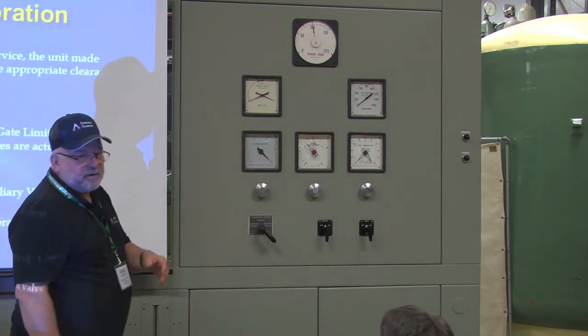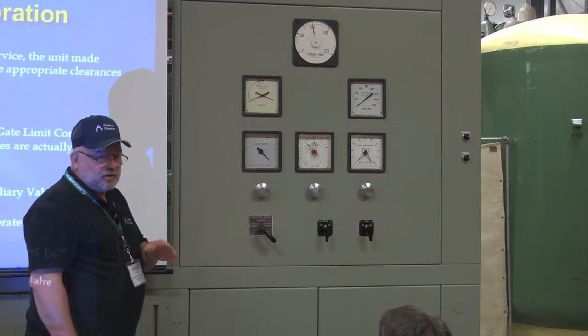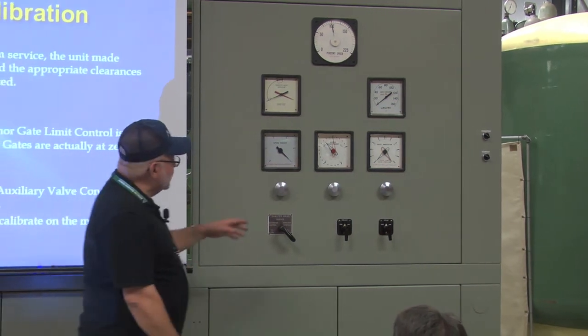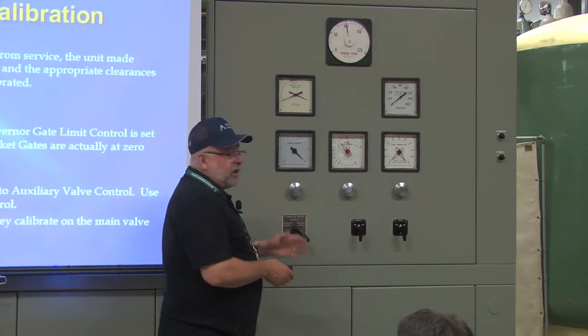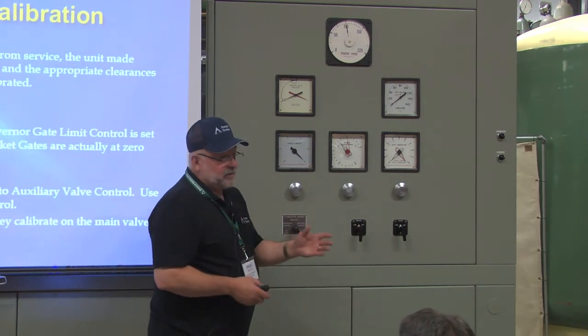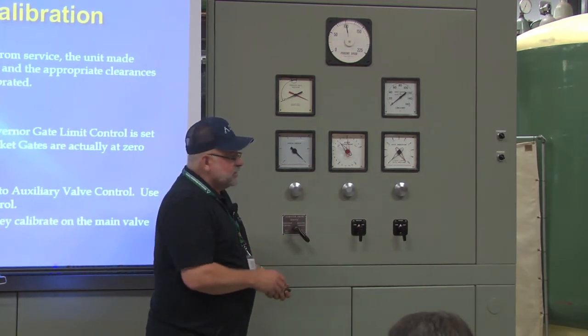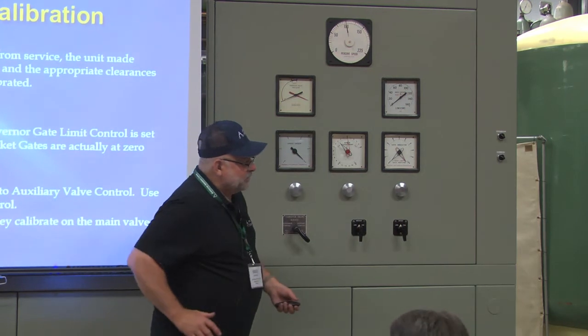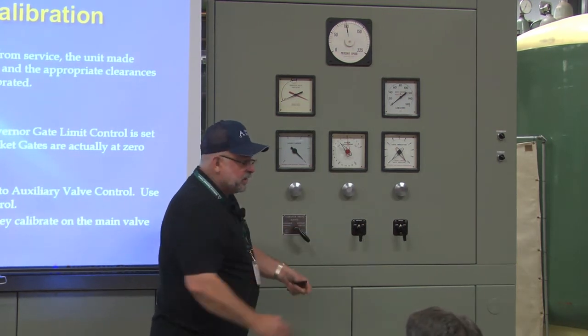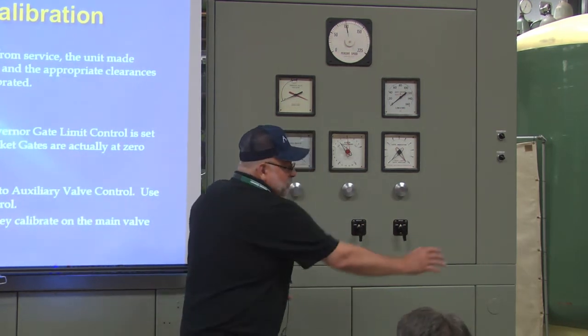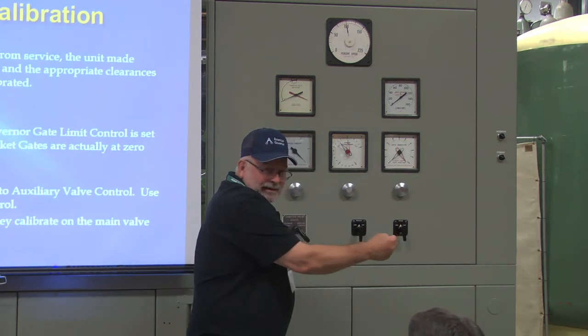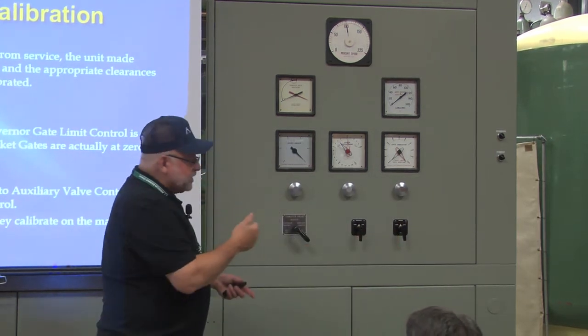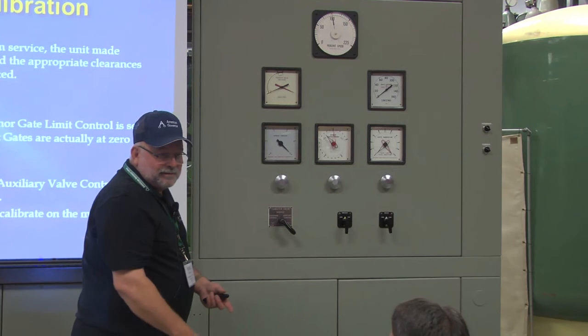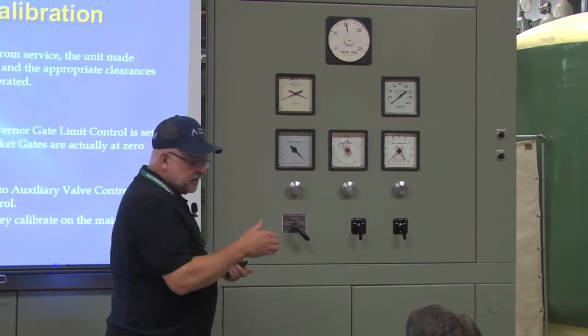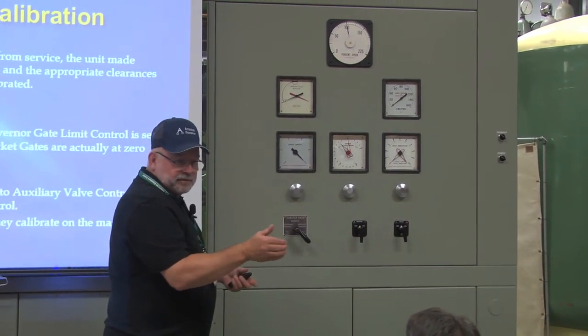So it's a 400 RPM unit, but I know for a fact it'll go about 728 RPM, all right? So it took off, and it's an impulse unit, so it doesn't take anything to roll it, it's in air, okay? So I scared the hell out of him. The desk is here, and the control board was there. I jumped over the top of the desk and reached between his legs and hit the 86E, and then to get to the governor, I have to go down another deck. So I'm hauling ass, because it's the only thing you can stop it with is the deflectors.